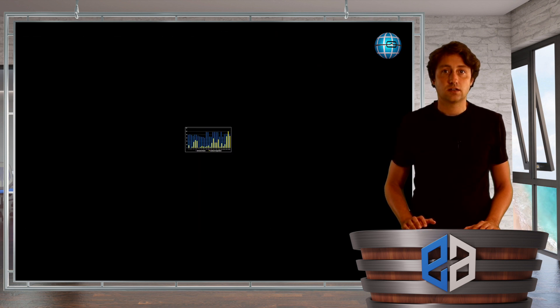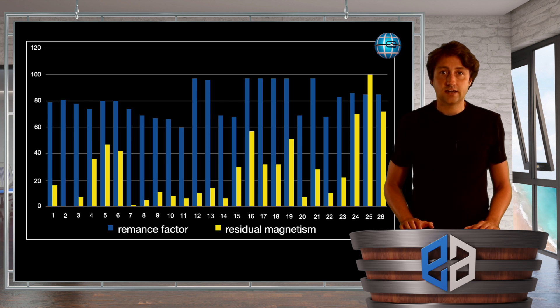And as an example we get a picture like this where in about half of the current transformer cores that we studied we measured a significant amount of residual magnetism.